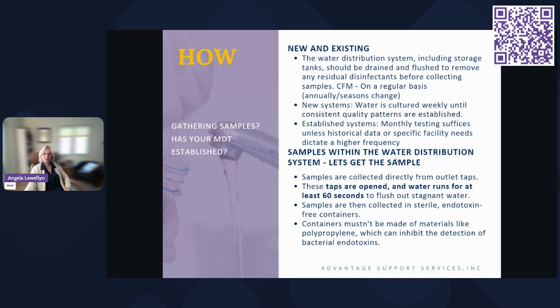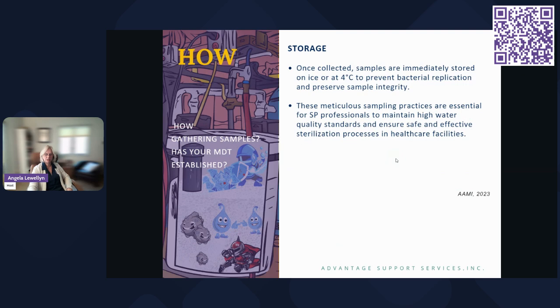Samples within the water distribution system — let's get a sample. Samples are collected directly from the outlet taps: you open the tap and run the water for 60 seconds, then collect it in endotoxin-free containers. The containers cannot be made of polypropylene, as it really inhibits the detection of endotoxins.